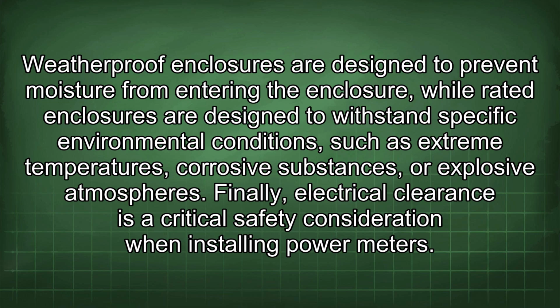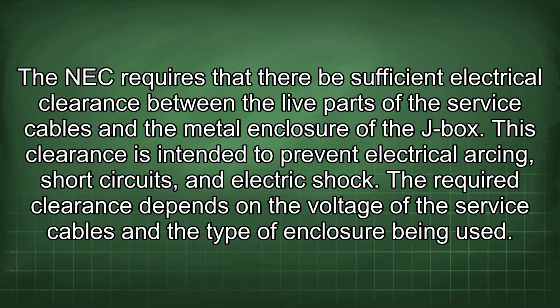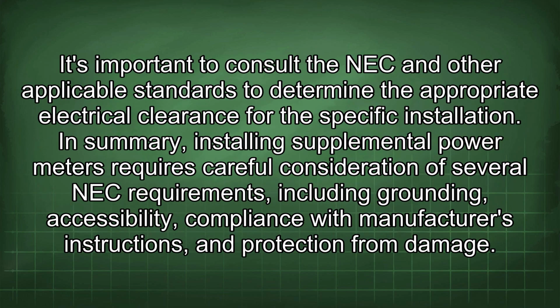Finally, electrical clearance is a critical safety consideration when installing power meters. The NEC requires that there be sufficient electrical clearance between the live parts of the service cables and the metal enclosure of the J-box. This clearance is intended to prevent electrical arcing, short circuits, and electric shock. The required clearance depends on the voltage of the service cables and the type of enclosure being used. It's important to consult the NEC and other applicable standards to determine the appropriate electrical clearance for the specific installation.